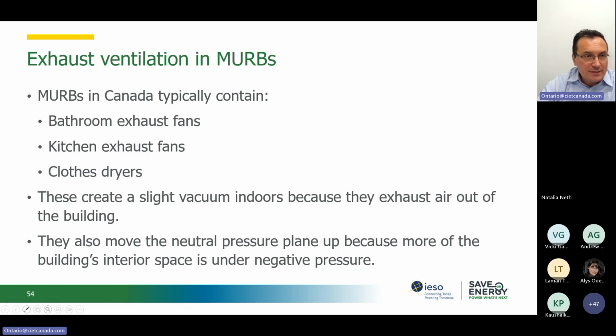So this exhaust, if it's not well balanced, will cause that negative pressure to drive the infiltration. But even if it's controlled, so we balance the amount of makeup air we bring to compensate for the exhaust, we still need to condition that air. Areas where we want to control this are usually kept under slightly negative pressure, so that if we have exhaust air, it's going to pull air from other spaces. For example, bathrooms will pull air from the living areas to replace it after it's exhausted.